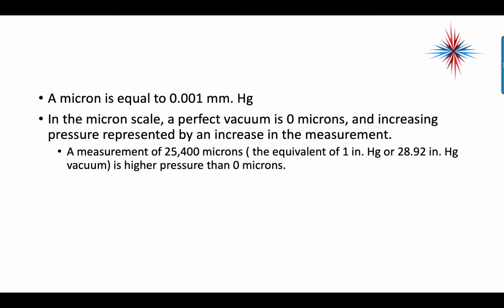In the micron scale, a perfect vacuum is 0 microns, and increasing pressure is represented by an increasing measurement. A measurement of 25,400 microns is 1 inch of mercury, or 28.92 inches of mercury vacuum. And that's a higher pressure than 0 microns.